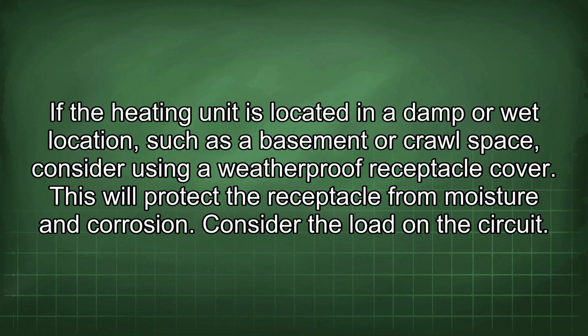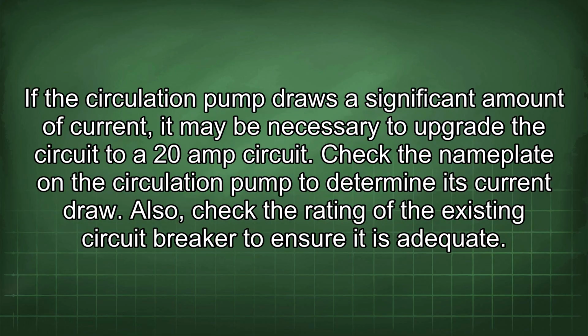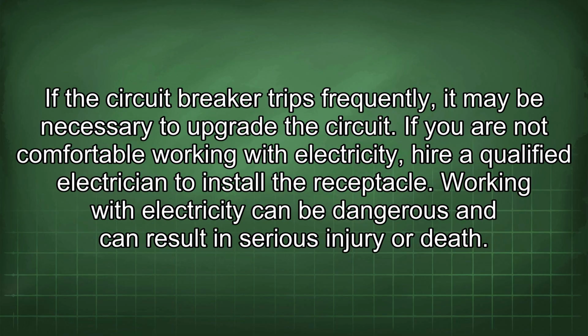Consider the load on the circuit. If the circulation pump draws a significant amount of current, it may be necessary to upgrade the circuit to a 20-amp circuit. Check the nameplate on the circulation pump to determine its current draw. Also, check the rating of the existing circuit breaker to ensure it is adequate. If the circuit breaker trips frequently, it may be necessary to upgrade the circuit.